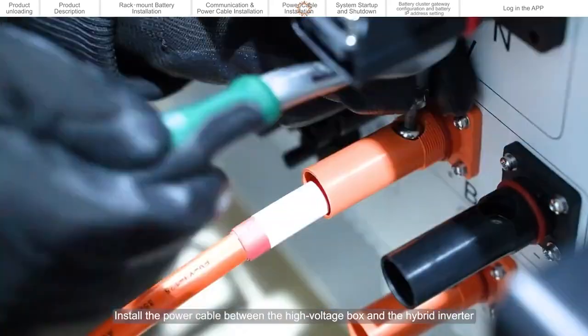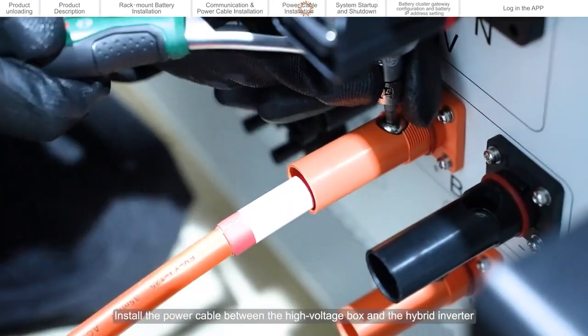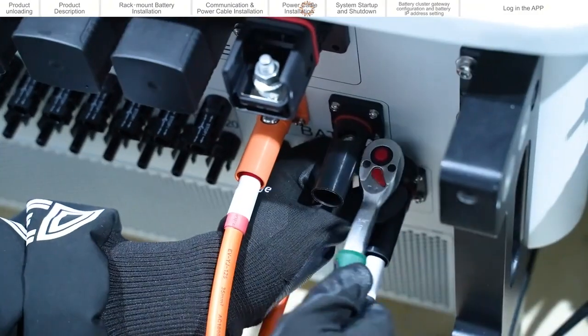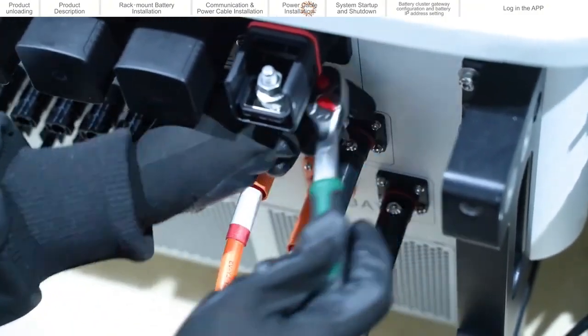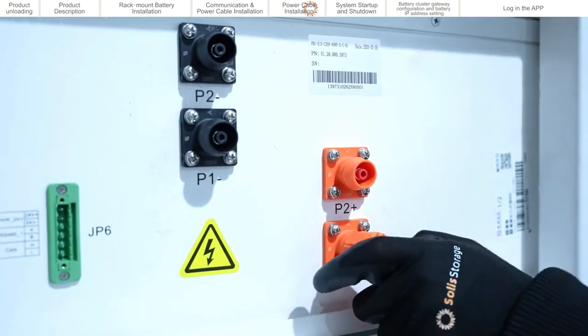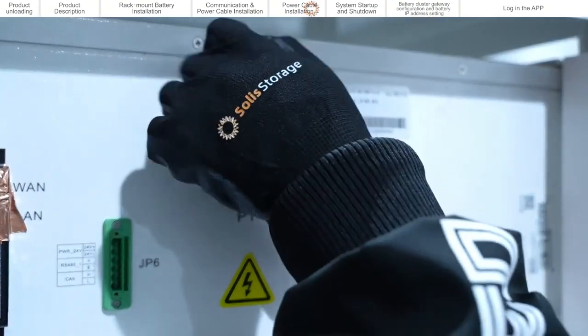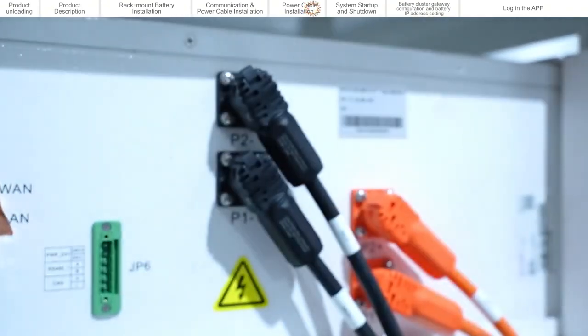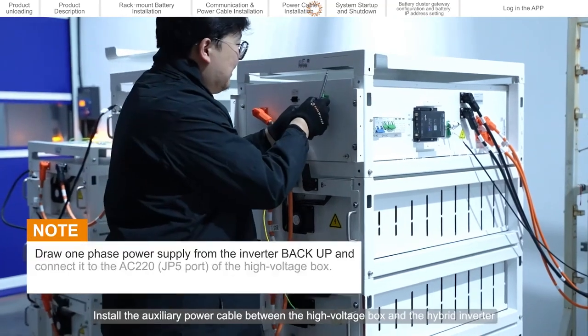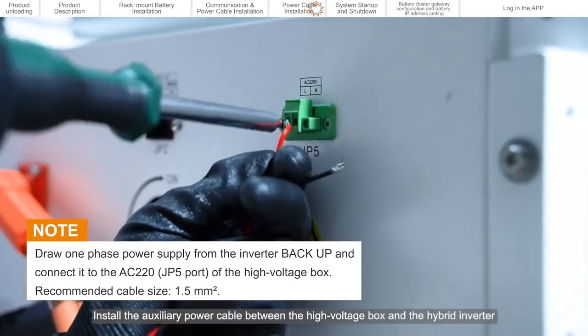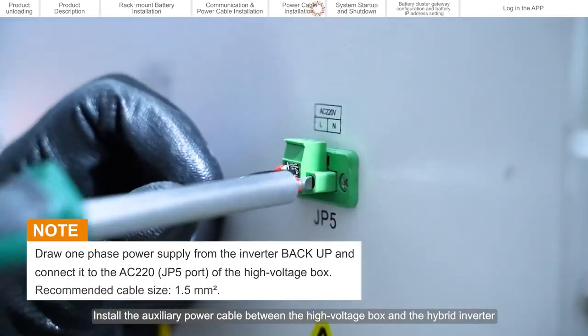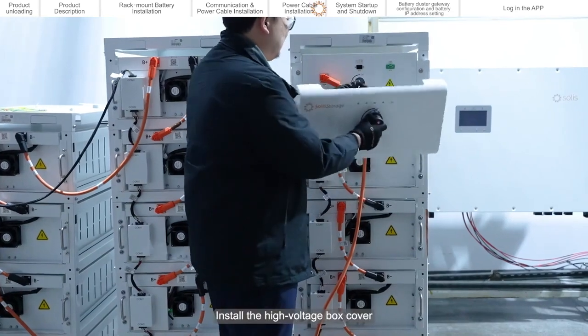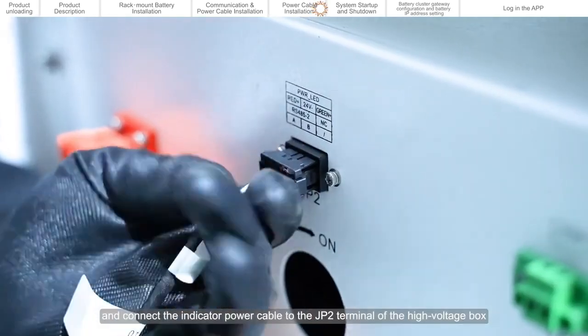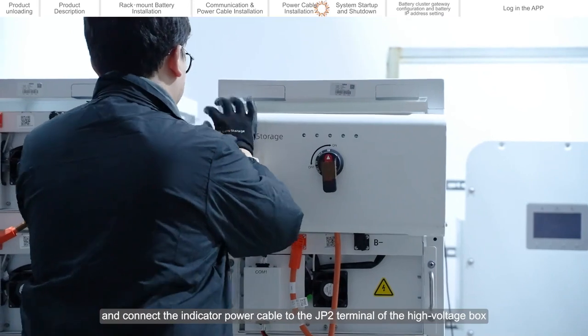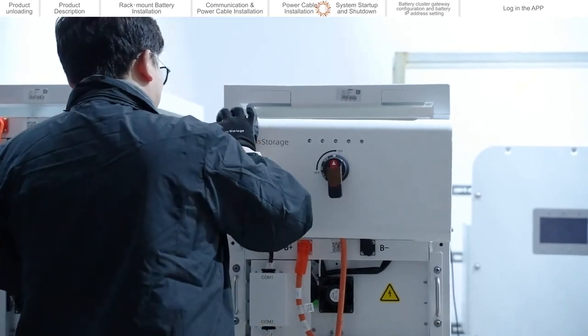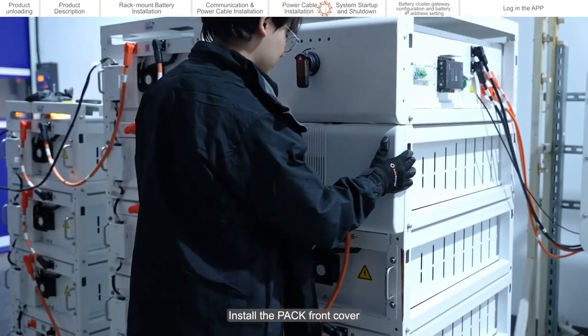Install the power cable between the high voltage box and the hybrid inverter. Install the auxiliary power cable between the high voltage box and the hybrid inverter. Install the high voltage box cover and connect the indicator power cable to the JP2 terminal of the high voltage box. Install the pack front cover.